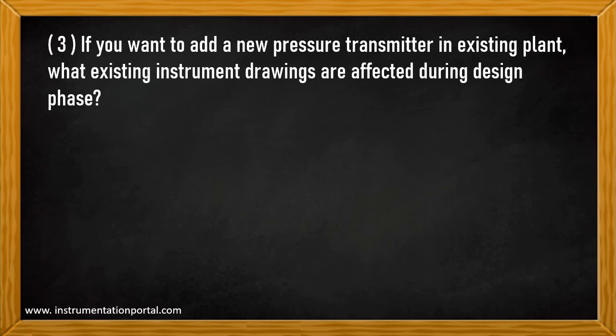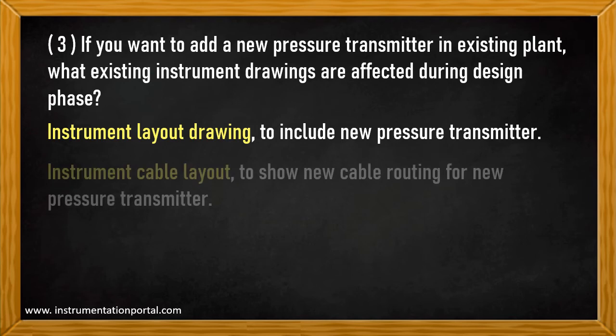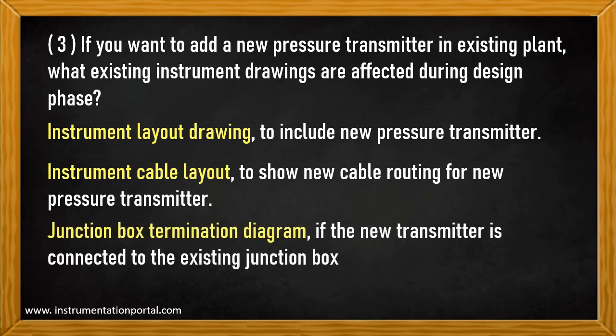Question number three: if you want to add a new pressure transmitter in an existing plant, what existing instrument drawings are affected during the design phase? First, the instrument layout drawing shall be revised to include the new pressure transmitter. The instrument cable layout must include new cable routing for the new pressure transmitter. The junction box termination diagram must show the new transmitter connected to the existing junction box — the terminal number previously intended for spare shall now indicate the new connection, showing that the terminal strips are now occupied. If a new junction box is needed, then a new drawing is required.